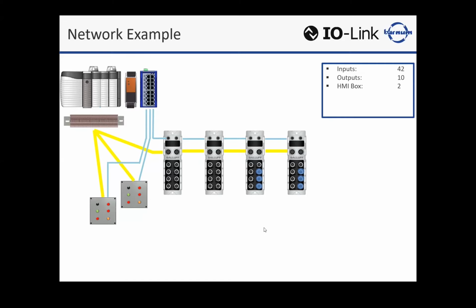Analog is, I know we got a lot of customers that want to do analog over these IP67. There are some products out there, obviously you can buy them, they're very expensive, but most often I do see people wire those ultimately back to the panel. So we'll add that analog back and maybe wire it back to the IO card. Yeah, I mean, we can go IP67, and I'll touch on that in just a minute. But yeah, I still see people, like you said, taking analog hardware back to the PLC rack.